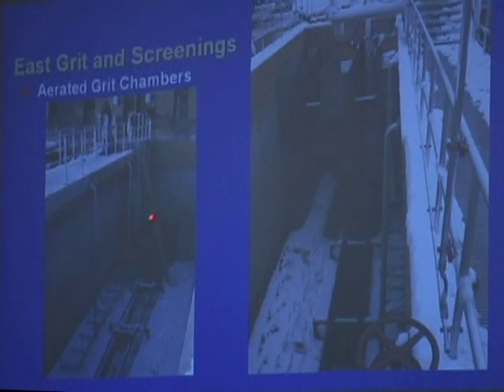And there is a valve here, which we'll take a look at when we get out there, for filling the tank, so that you're not taking a full load of wastewater head from this location and dropping it onto an empty tank, potentially doing some jarring of the grit collection system. So you can fill the tank using this valve here. The headers that feed the air into the system are located here.